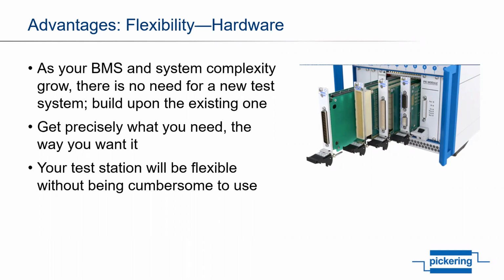Due to the number of vendors offering PXI, you can generally find a module that will provide the functionality that you require, or will develop it for your needs. You are not limited to a pre-configured system that a single vendor can offer that either falls short of your full requirements or far exceeds with the associated cost implications. This all means that your test station can be flexible without being cumbersome.